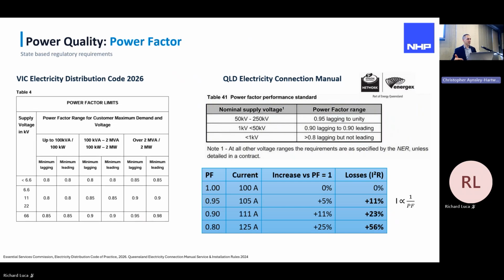At a power factor of 1, the installation is drawing 100 amps. But if we're reducing our efficiency to 80%, 0.8 power factor, we now need 125 amps of current to service the same load because of the wasted energy in the system. So an increase of 25%, I squared R losses over 50%. So the utilities don't want all businesses running at a very low power factor, because they'll have to beef up the infrastructure and costs go up for them too.